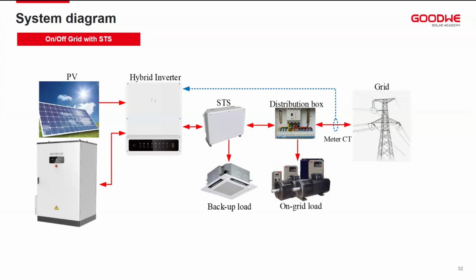Now, first off, we have the on or the off-grid installation using the inverter, the ET, and the STS. This is just a single inverter. Mark you, the inverter will be coming with the smart meter as one of the accessories with the inverter. So the GM330 smart meter, it's a 3-phase smart meter, will be coming with the inverter. All you need to do is purchase a third-party CT as long as the secondary rating is 5 amps and you're good to go.